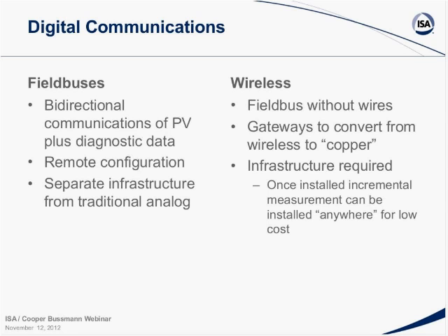Field buses, because they're bidirectional, allow remote configuration. The challenge with going from an analog system to field bus is that some of the infrastructure must be different. Some buses are designed so you can reuse the cable, but the communications cards at either end have to be protocol-specific.